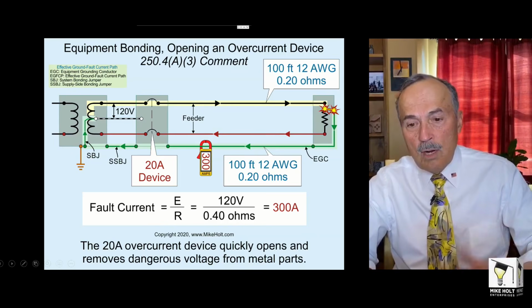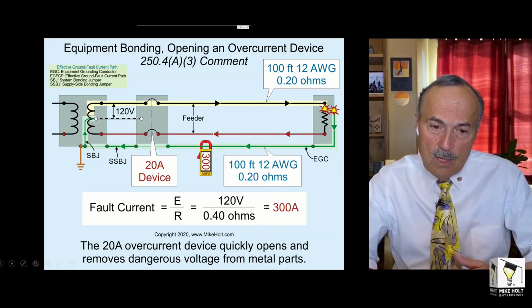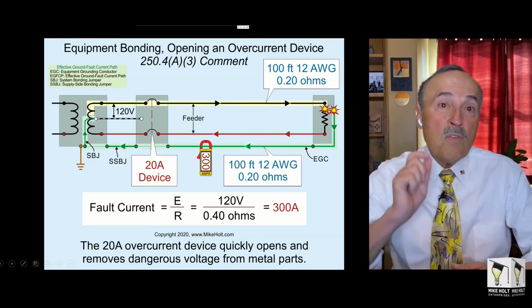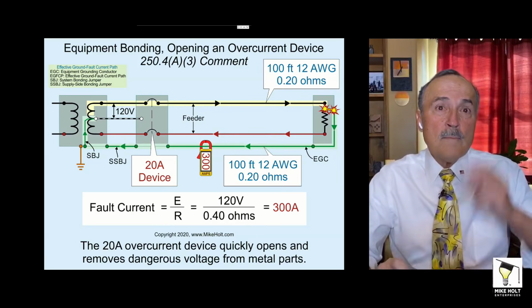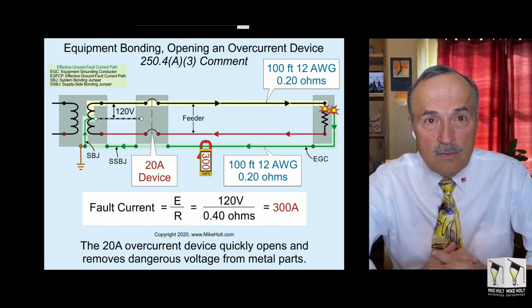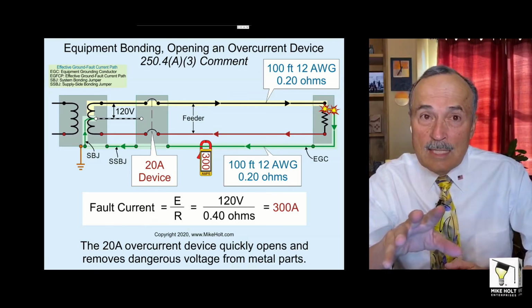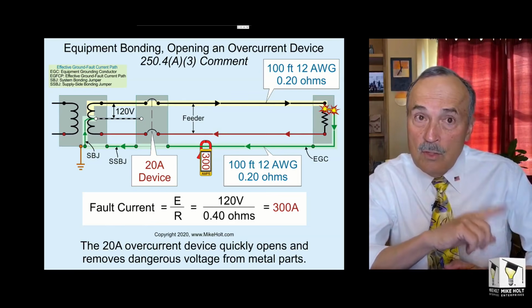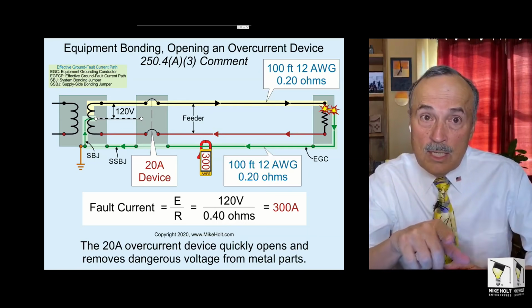Electrons leave the source. There's a ground fault. They travel on the effective ground fault current path to get back to the source. It provides a low impedance path to do what? Open the protection device. Now, if I said that too fast, that means you didn't see the first video and you didn't see the second video. You should be able to understand what I'm saying now.